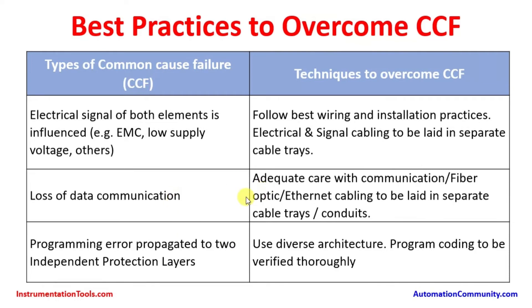Fiber optic and Ethernet communication cabling must also be laid in separate cable trays with adequate care and must not be mixed with power cables such as 3.3 kV, 6.6 kV, or 11 kV. Higher voltage power cables and signal cables cannot run together.